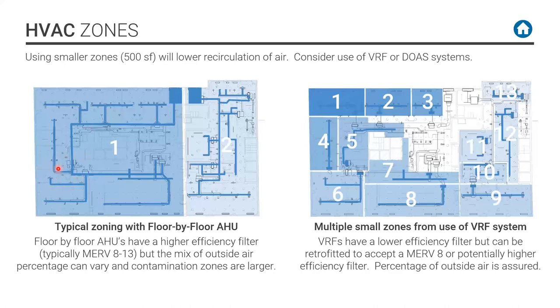Also, if you have a VAV system, as the cooling load reduces, you get less air, therefore less outside air dilution in the space. If you go to a VRF or a DOAS system, you have a smaller zone, and what you can't see on the plan is that we have a fresh air connection to each of these boxes, and you get an assured quantity of outside air. So the dilution is always spot on in the DOAS system. The downside is it's difficult to get, I shouldn't say you can't, a MERV 13 filter in these small units. They have very little static pressure.